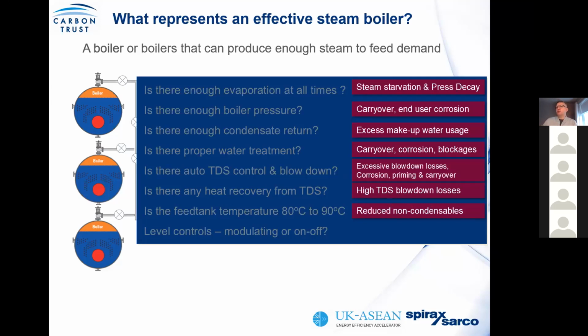And then your level controls, is it modulating, is it on or off? Even we have found for customers where they have modulation controls installed, they act in on-off by virtue of the way the boiler responds to the process steam demands. So in other words, load matching and swell. So in other words, how does the boiler operate in response to the process?